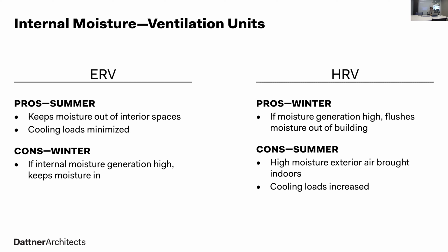So if the total humidity level for all 70 apartments being served by any one ERV gets too high, they can slow down the enthalpy wheel and more latent heat will be expelled from the building. It does mean that we lose some sensible heat as well, lose a little bit of energy, we'll have to use a little more heat. So that mitigation technique is really limited to when there's a danger of condensation, but based on the analysis, that should be a pretty infrequent scenario.